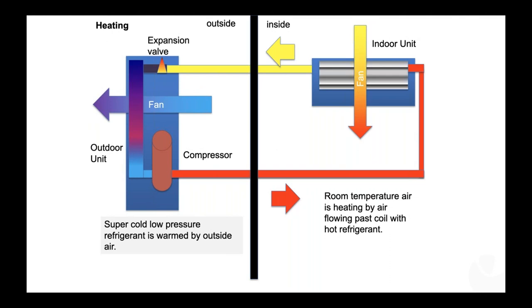If you choose not to install all the heat pump equipment that would be required to meet your peak load at super cold temperatures, that's fine. Use your heat pump to the maximum extent you can. Keep it running all the way through all those extremely cold weather events, and supplement as you need to, whether that's with a wood stove or any other heat source for that matter, for those brief periods of time when the heat pump that you've selected might not be able to keep up with a full load, if you haven't selected enough heat pumps to do that.